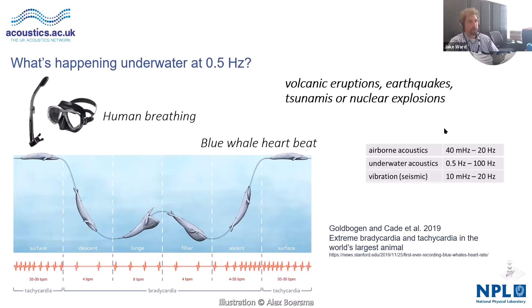The laser piston phone, or a piston phone, is one of many options we have for calibrating hydrophones. So other options are available. And for anyone who likes British standards, there's an absolute epic here, a 60-pager, part 2 of BS 60565-2, which is procedures for low frequency pressure calibration. So you can have a vibrating column, you can dunk a hydrophone, you can use hydrostatic excitation. You could, it is fundamentally introducing a change of pressure on the transducer. Or a coupler reciprocity, where we have 3 devices within a closed chamber, and we transmit and receive on different combinations of them and measure voltage and current.